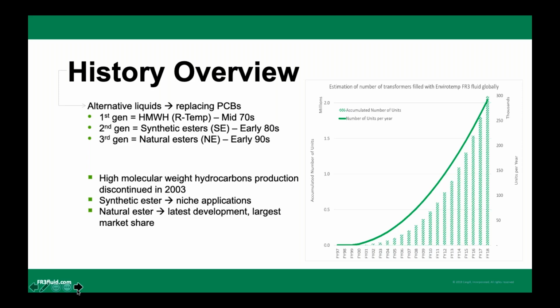Second, when we talk about the other technology, like what the Western world used to think, they said, look, the transformer, when it was invented, it was a dry type. We engineers made it liquid filled so that we can take the maximum possible efficiency and maximum possible power out of it. So why don't we continue developing or exploring available liquids which can be fire resistant? And that's how the birth of alternate liquids came. In the initial days, Cooper Power Systems developed R-Temp, which was nothing but high molecular weight hydrocarbons. They were heavier and the transformer needs to be derated.